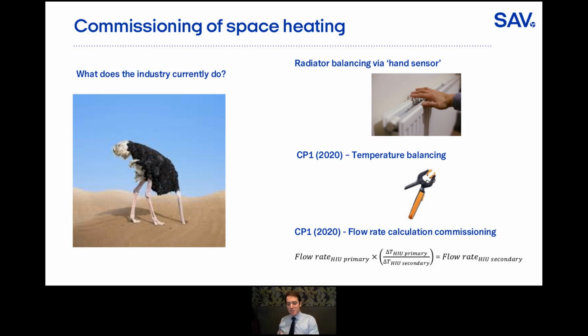When looking at commissioning and verifying HIUs, there are three different areas you need to look at. You have DHW, keep warm, and space heating. It's generally now started to be accepted the different ways that we can commission the DHW and the keep warm to ensure we get those low return temperatures. The real issue comes when we look at the space heating side.